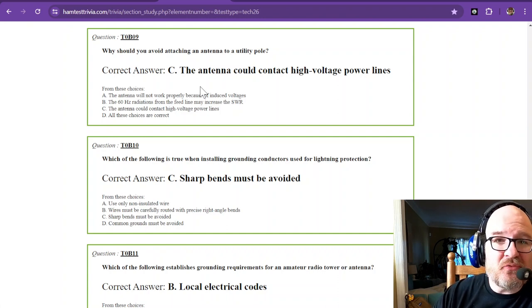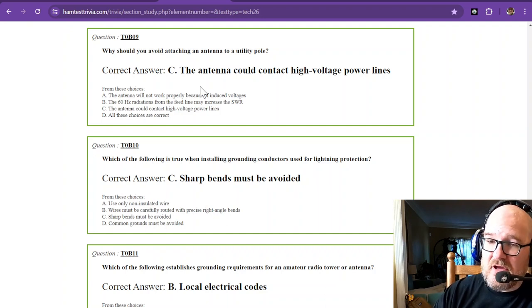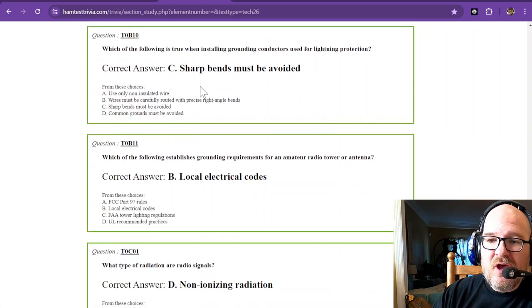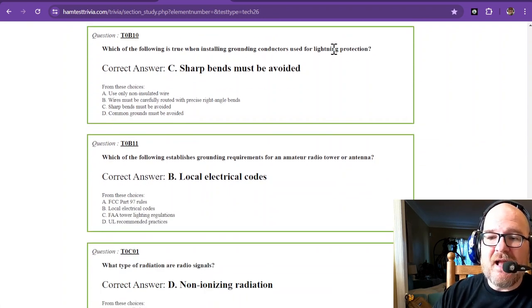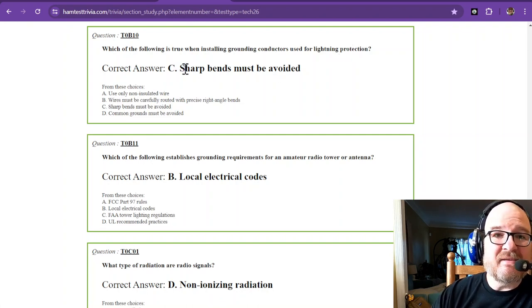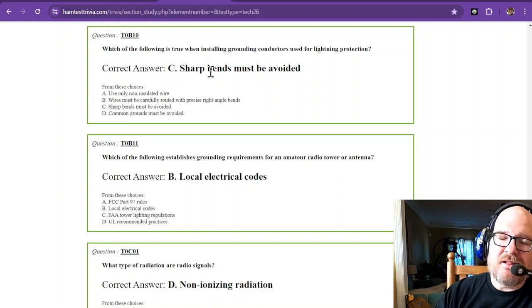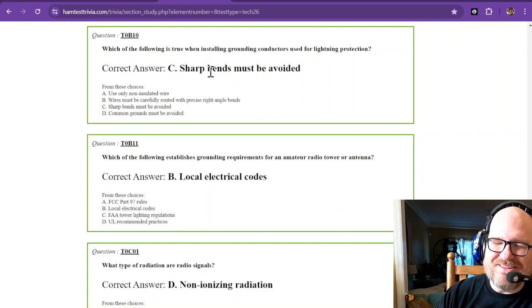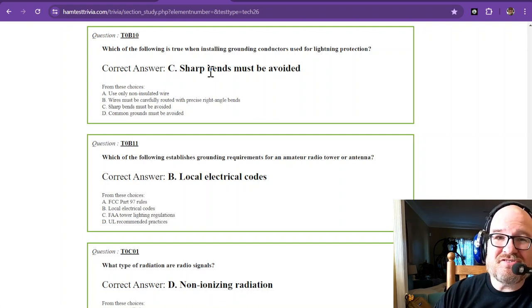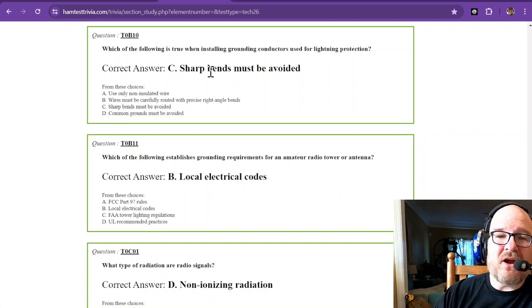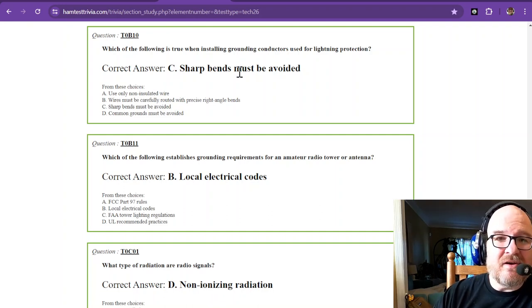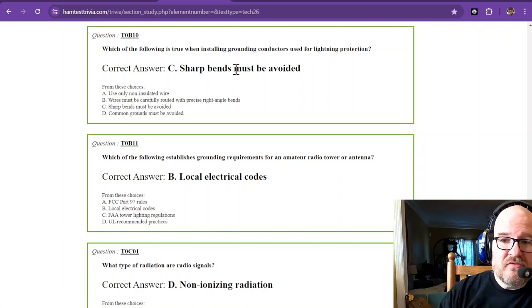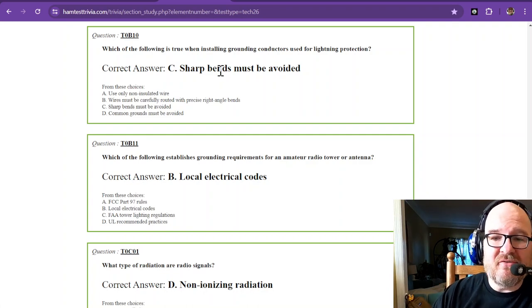Which of the following is true when installing grounding conductors used for lightning protection? Sharp bends must be avoided. You would think that electricity wouldn't mind, but lightning strikes—the electrical portion of those spans anywhere from DC all the way up through several megahertz and maybe even gigahertz. And so sharp bends are going to cause an impedance problem. You want it to be as direct as possible to the ground. Sharp bends must be avoided.